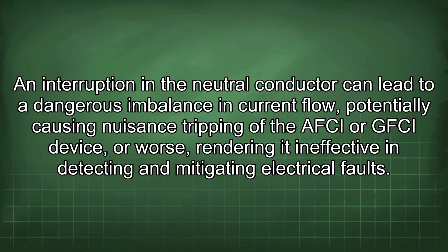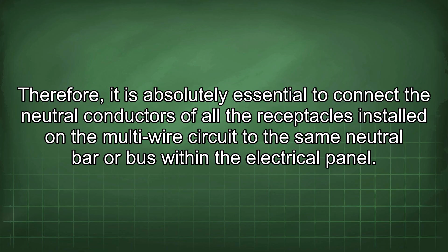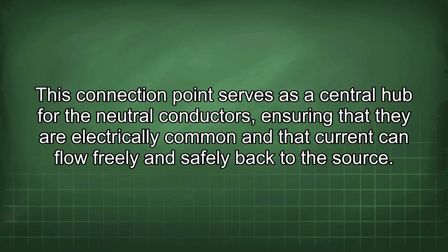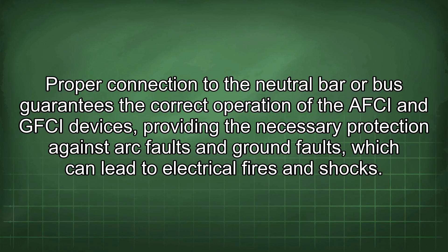Therefore, it is absolutely essential to connect the neutral conductors of all the receptacles installed on the multi-wire circuit to the same neutral bar or bus within the electrical panel. This connection point serves as a central hub for the neutral conductors, ensuring that they are electrically common and that current can flow freely and safely back to the source. Proper connection to the neutral bar or bus guarantees the correct operation of the AFCI and GFCI devices, providing the necessary protection against arc faults and ground faults, which can lead to electrical fires and shocks. The importance of maintaining a continuous and uninterrupted neutral conductor in multi-wire circuits with AFCI and GFCI protection cannot be overstated, as it is fundamental to the safety and reliability of the electrical system.